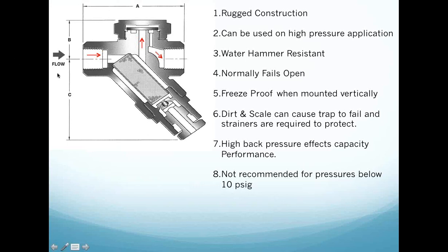This particular trap, as the steam gives up its latent heat of vaporization and it condenses, which is exactly what we're trying to allow it to do, the condensate moves into the steam trap body, this thermodynamic disc steam trap body, and it actually lifts that disc element, and it goes across the seat and out to the discharge. Now, if I put my thumb over the end of a water hose on the weekend when I was washing my car, the velocity would increase, and if I had the ability to measure, the pressure would drop.